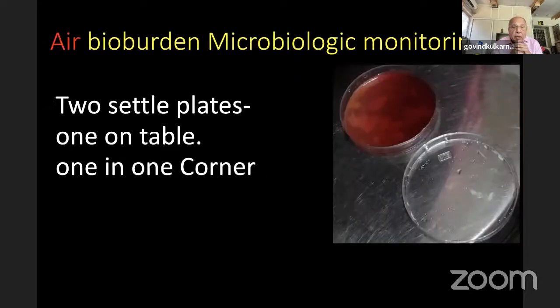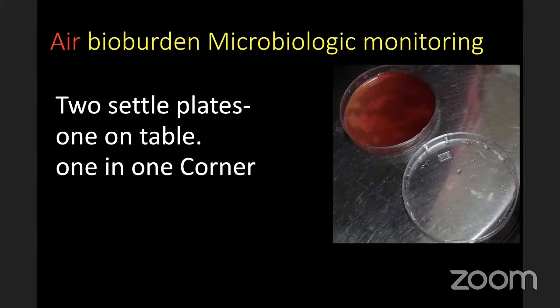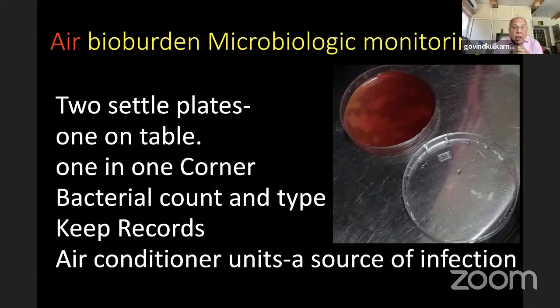Air bioburden: you should use microbiological monitoring. Use 2 settle plates, one on the table, one in the corner of the operation room. Bacterial count and type must be recorded, and keep records of all these things for medico-legal purposes. Air conditioner units in the OR are a source of infection, and therefore, as far as possible, do not use an air conditioner unit in the OR. But if you have to use one in a small hospital, then you must maintain it properly and wash it every week.